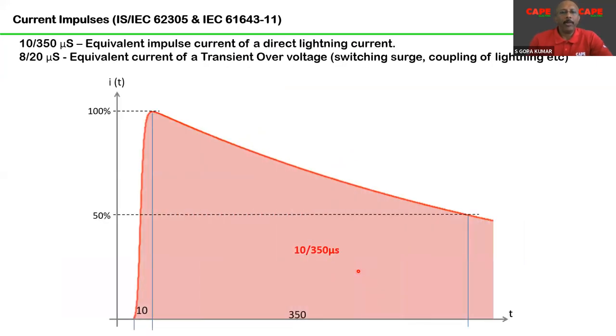When you look at lightning protection, always people ask, what is this 10 by 350 microseconds? The energy content of lightning has been generated in a laboratory as a wave shape. Finally, whatever the components which we are using need to be tested. For that testing, we need to have a standardized energy form so that all manufacturers can be at the same level to do the test.